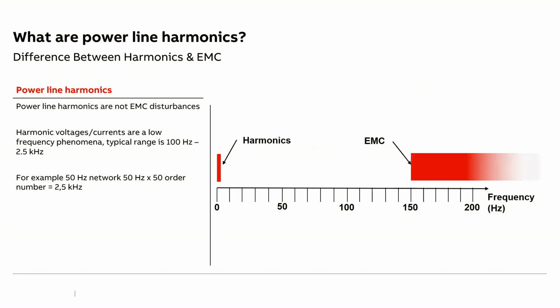Now, as I said, we will cover a little bit more detail about harmonics and EMC. EMC and harmonics are basically disturbances. These are electrical noise. These are unwanted signals. However, harmonics is different and EMC is different. Both are noise, both are disturbances, unwanted signals, but both are different. Harmonics is a low frequency signal, mostly restricted up to 3 kilohertz, and EMC is a high frequency signal. It is also known as radio frequency interference. The name itself suggests that it is a high frequency signal, and it is normally above 150 kilohertz. Both create disturbances and problems, but both are different, so the mitigation technique for each is also different.